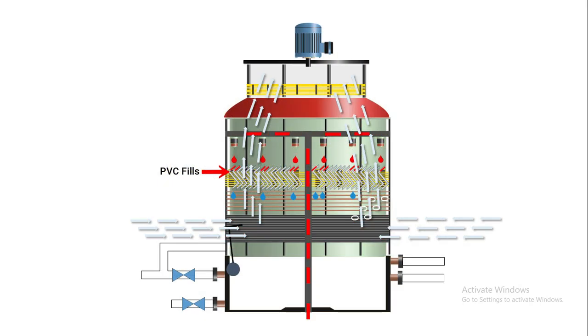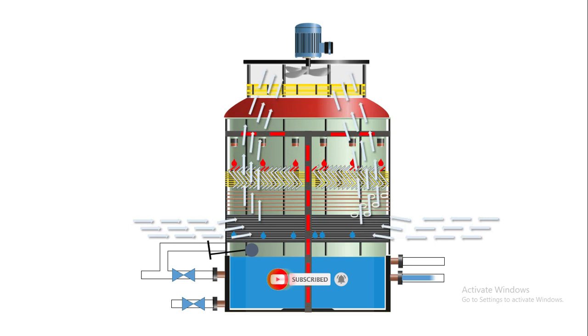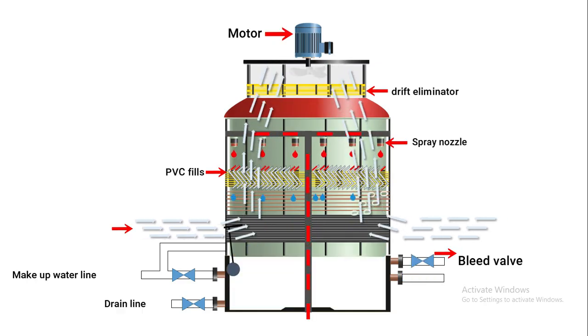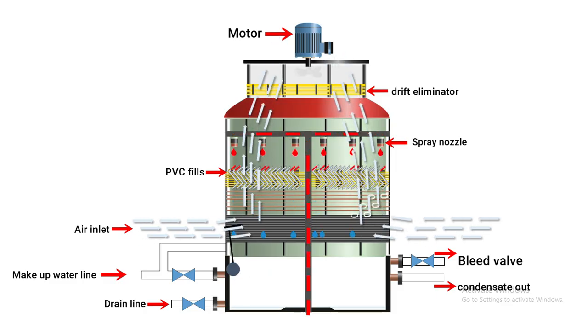So when the water is separated it falls on PVC fillings. PVC fillings are shaped like honeycomb. When water falls from above instead of falling directly downwards it flows slowly. At the same time fan runs which pulls the air outside and pushes it across the PVC fillings. Because of this the water comes down slowly, there is better and longer contact between air and water which increases the rate of evaporation.